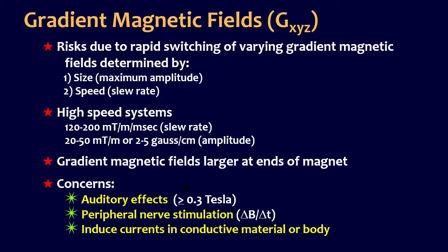Anyway, so in going to the gradient magnetic fields, I think in the beginning when we all knew about the right-hand rule, many of you who are X-ray technologists, we thought with this changing magnetic field that we would see more burns due to induced currents, but as Dr. Kugel showed nicely, it's really the RF that we have to be concerned about. The auditory effects are real.